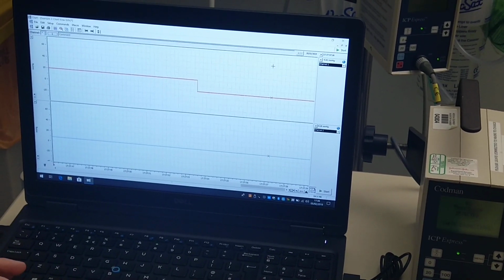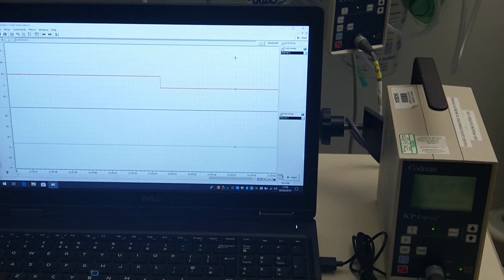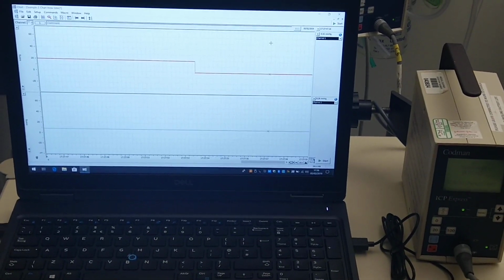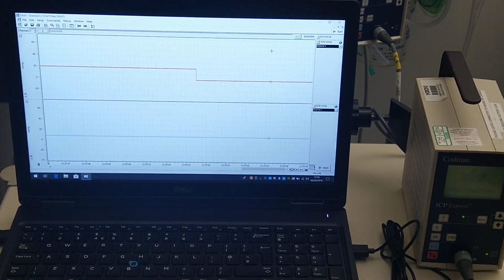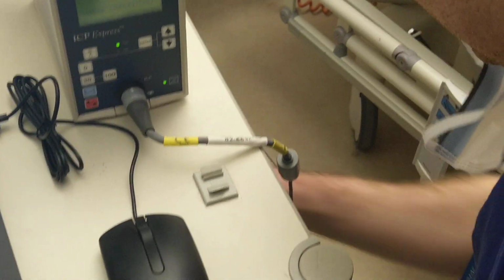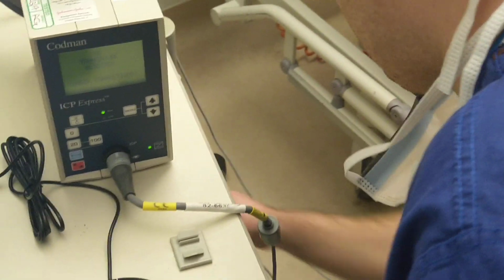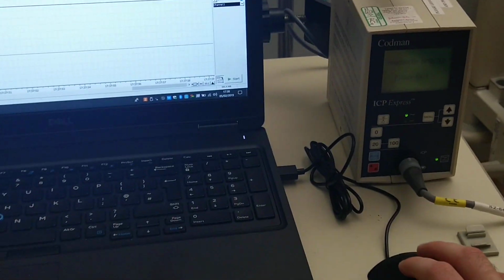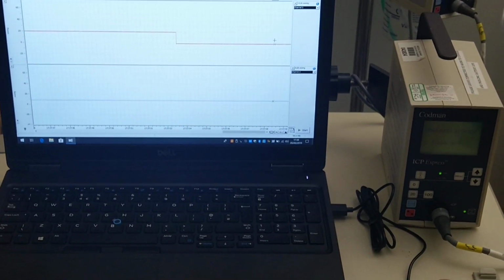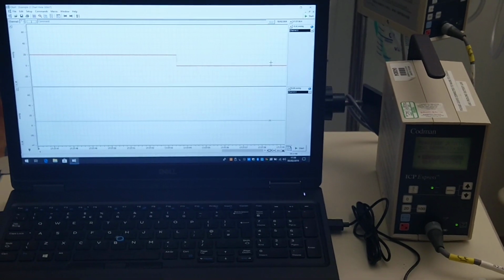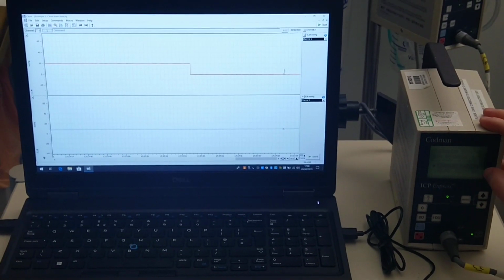Now, I'm going to take the patient transducer cable from the patient. Actually, we can leave that. And what I'm going to do is plug the ICP monitor from here into that. So now you'll see transducer detected appears on the monitor, and in a second it should say transducer detected, 0 reference. I know in this case the reference is 497, not 533.